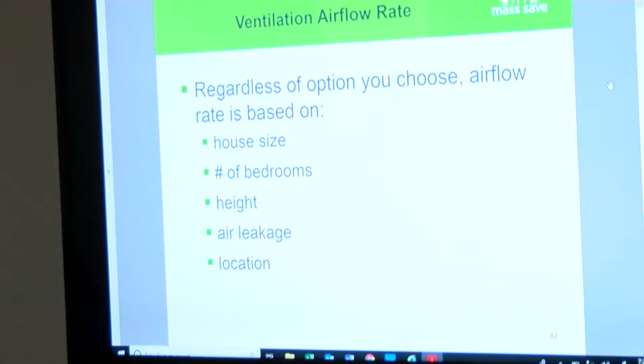And we add non-tamper stickers to them because they're supposed to be a set and tested device. Excellent. So again, the ventilation airflow rate that Peter was just discussing is discussed here in this slide. So the house size, the number of bedrooms, the height of the walls, the air leakage, and the location is all discussed, all calculated at the end.